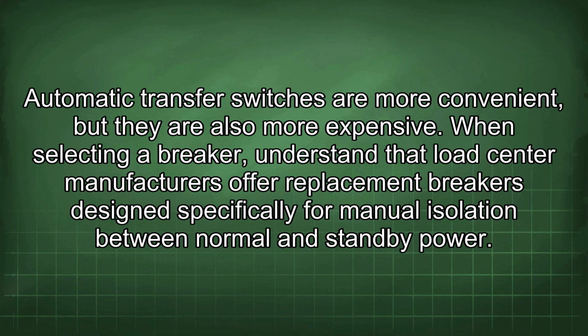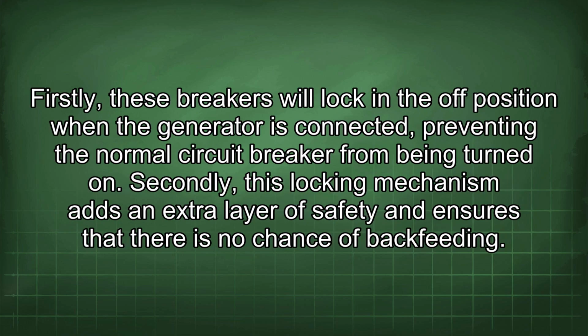When selecting a breaker, understand that load center manufacturers offer replacement breakers designed specifically for manual isolation between normal and standby power. Firstly, these breakers will lock in the off position when the generator is connected, preventing the normal circuit breaker from being turned on. Secondly, this locking mechanism adds an extra layer of safety and ensures that there is no chance of backfeeding.